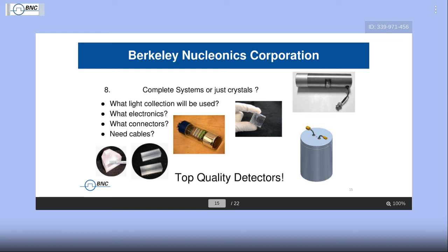It's the bialkali surface, and this is what takes the scintillation photons, the photoelectrons, and starts turning them into real usable voltages like 1, 2, 3, 4, 5 volts. Something we can actually make electronic measurements with.